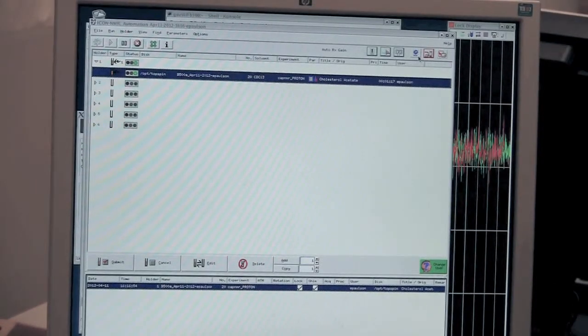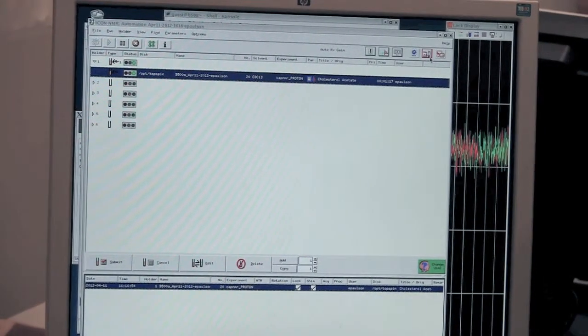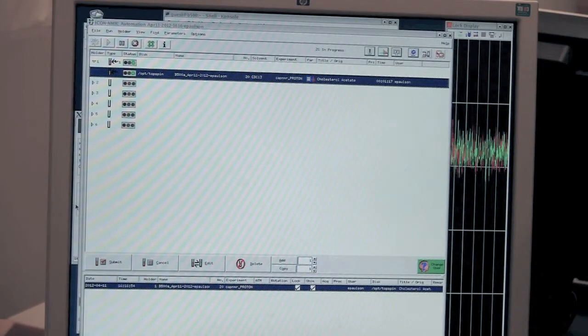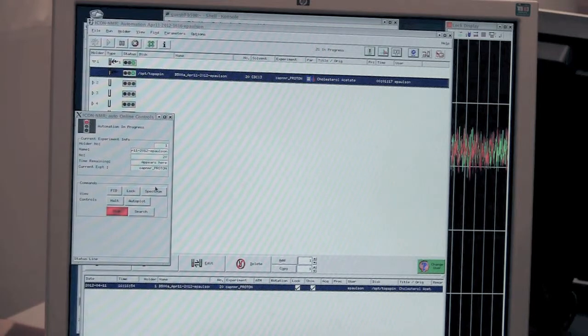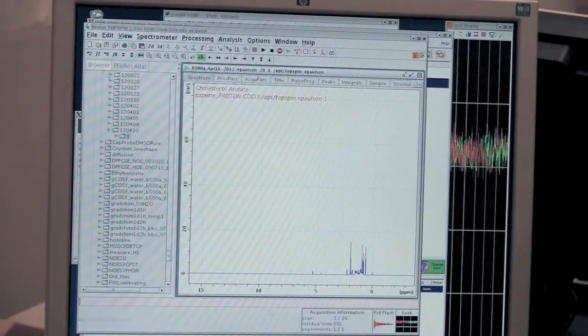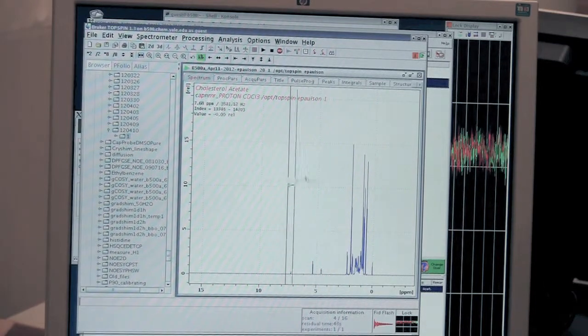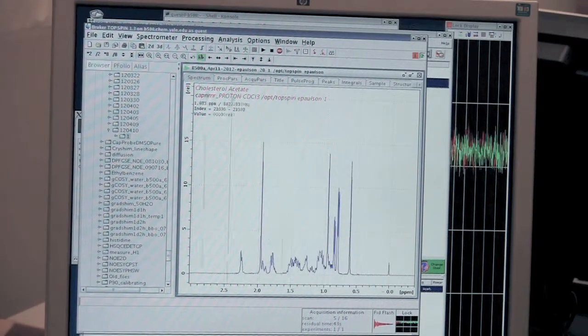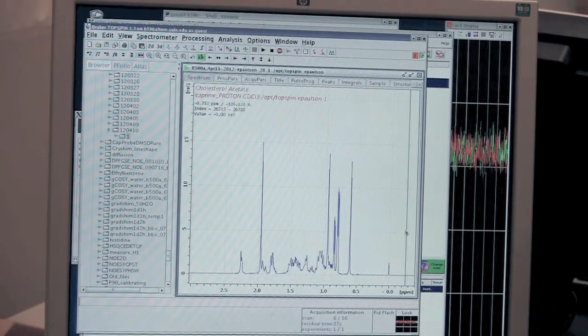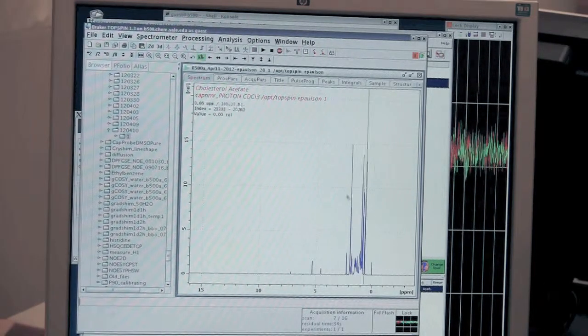It's doing the receiver gain adjustment like normal, and then it's going to go in and start collecting data like normal. Just like on a normal system, if you want to, you can click on spectrum after it's started to look at a snapshot of the spectrum while it's underway. So I will go ahead and do that. And it should bring up the spectrum as it normally does. You should be able to get a data set that looks reasonable. The line width might be a little bit broader depending on your shimming than it is on a normal NMR probe, but you should be able to get under 2 Hertz line width.